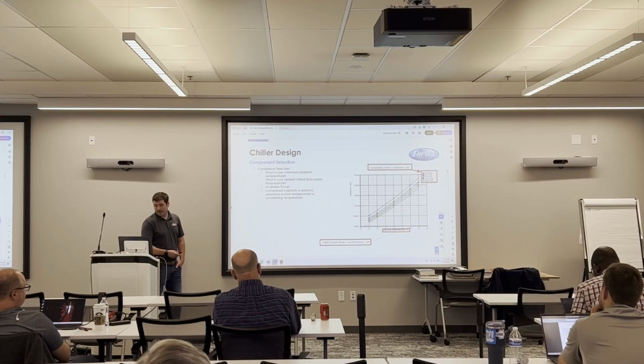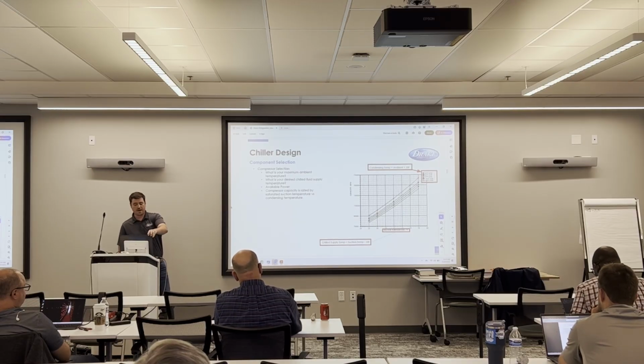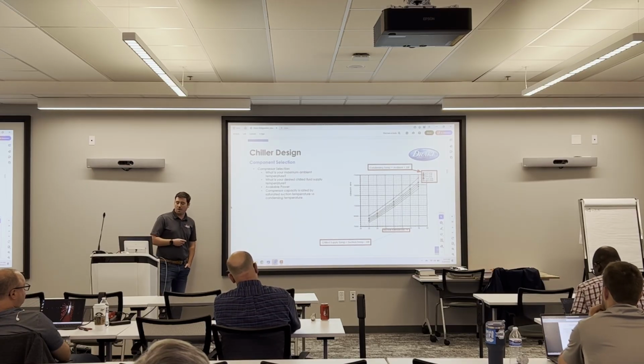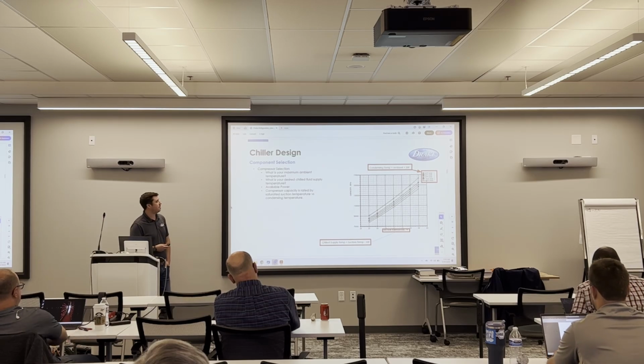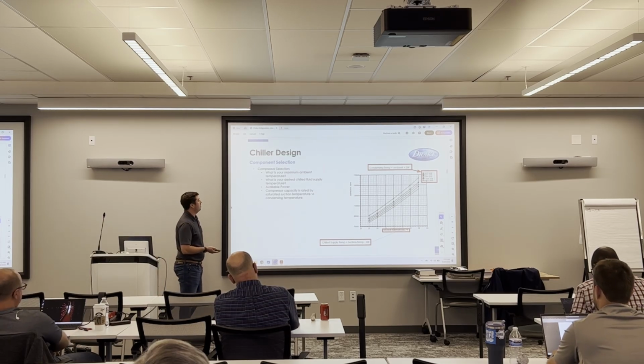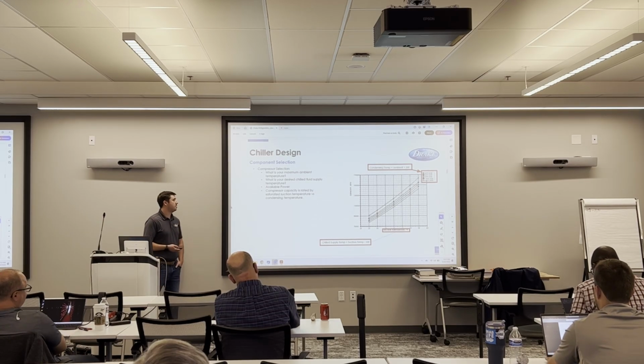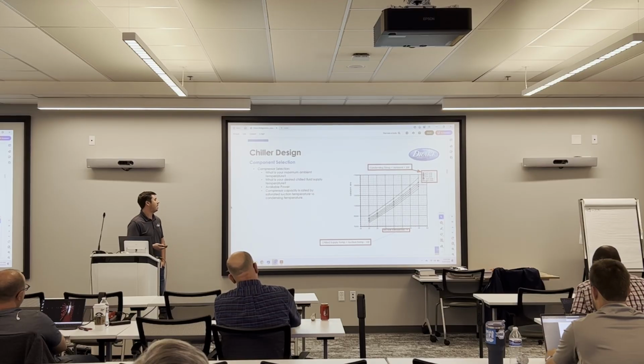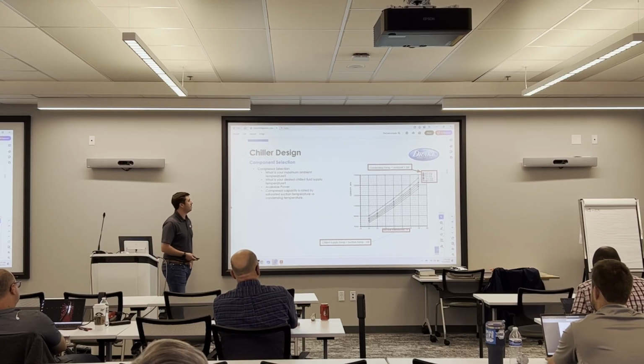We're going to need to know the maximum ambient temperature that the chiller is going to be operating in. We're going to want to know what chilled fluid supply temperature the customer desires. We should know what power the customer has on site or available to them. And then your compressor capacity is going to be rated by your saturated suction temperature and your condensing temperature. So what does that mean?